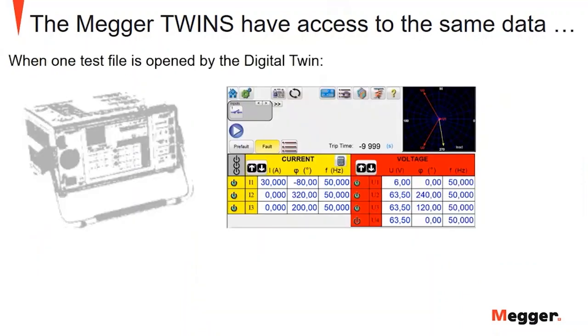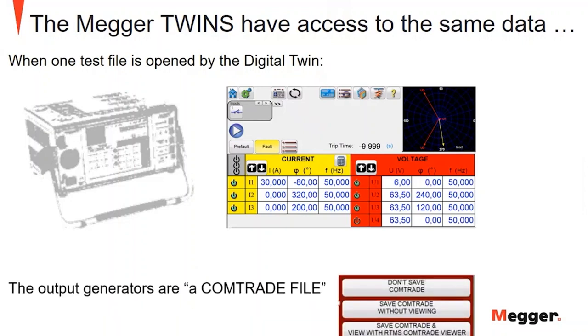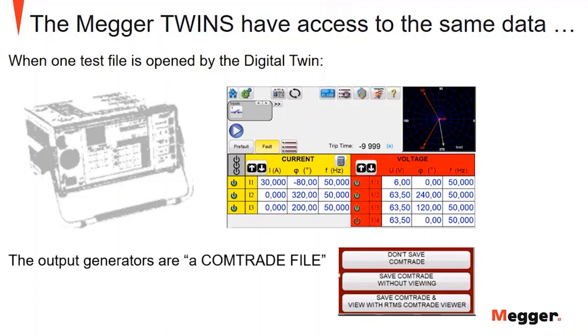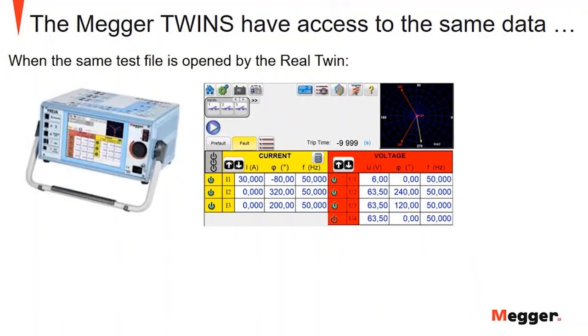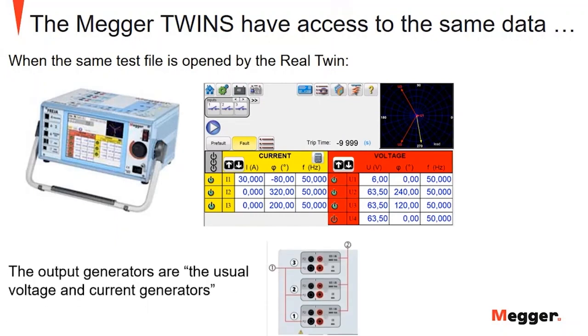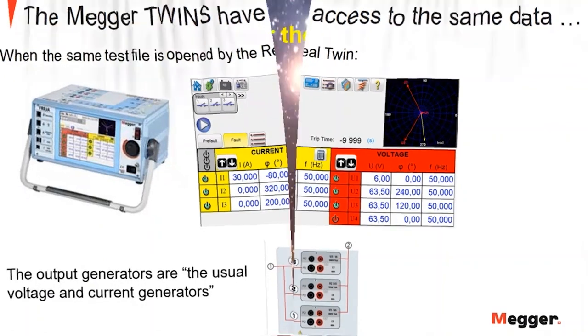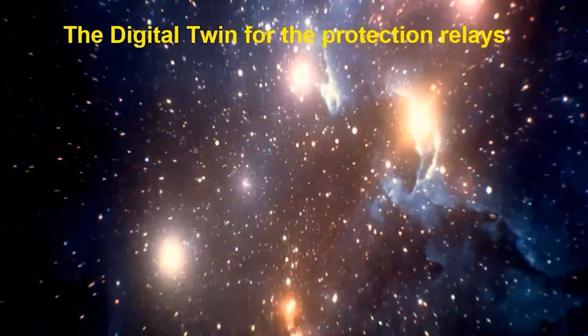So one test file, again, I have to explain this again, I think. When one test file is opened by the digital twin, the output generators of the digital twin are a ComTrade file. And when the same test file is opened by the real twin, the output generators are the usual voltage and current generators that we are comfortable with, for the protection relay.